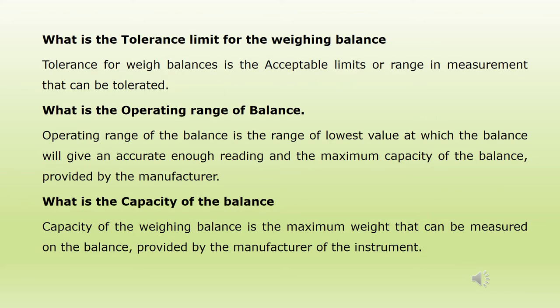What is the tolerance limit for a weighing balance? The tolerance limit is the acceptable limit or range in measurement that can be tolerated. What is the operating range of a balance? The operating range is the range from the lowest value at which the balance gives an accurate enough reading to the maximum capacity provided by the manufacturer. What is the capacity of the balance? The capacity is the maximum weight that can be measured on the balance, as provided by the manufacturer.